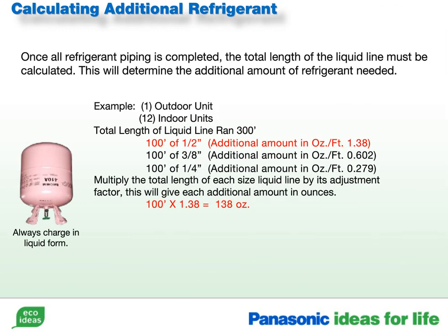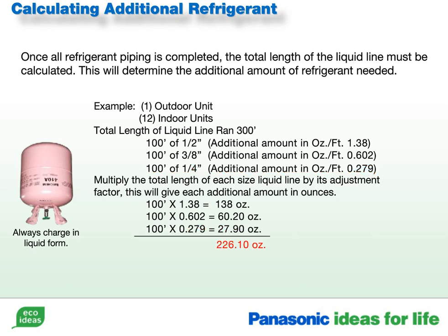The multiplier for half-inch is 1.38 ounces per foot. So we multiply 100 times 1.38, which equals 138 ounces. For 3/8, we multiply 100 times 0.602. That equals 60.20 ounces. And for quarter-inch, multiply 100 times 0.279, and that equals 27.90 ounces. Add up the three totals, and we end up with 226.10 ounces. Divide the total by 16 for a total of 14 pounds 2 ounces. That's the total amount of additional refrigerant that will need to be added for a proper charge.